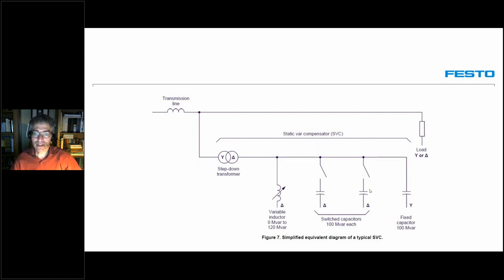Our SVC will be composed of fixed capacitors — in this case one fixed capacitor of 100 megavar — then two switched capacitors of 100 megavar each, which can be inserted or not in the circuit, and finally a variable inductor that can change from 0 to 120 megavar. Why use a variable inductor combined with capacitors instead of just variable capacitors? Simply because it's technically difficult to produce a reliable variable capacitor, so the capacitors are fixed in nature, while a variable inductor is much easier to build. This lets us absorb some of the reactive power produced by the capacitors, and the two working in tandem allow us to achieve any value of reactive power we need.